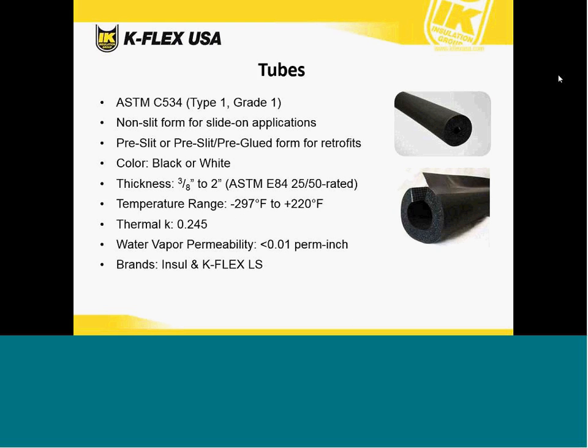The tubes conform with ASTM standard C534, Type 1, Grade 1, non-slit form for slide-on applications, or pre-slit, pre-glue for retrofits. The top picture is the non-slit form. The bottom picture is the pre-slit with the overlap tape. So you can see you have the peel and stick adhesive on the longitudinal seam, as well as on the overlap tape, which provides extra seam security and a layer of protection against water penetrating through that seam.